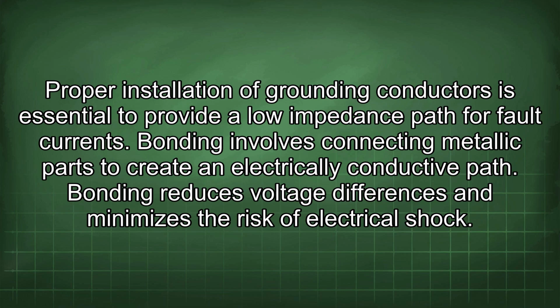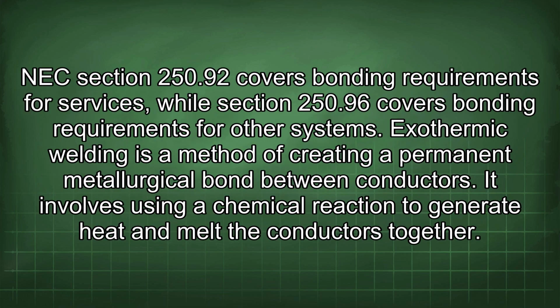Bonding involves connecting metallic parts to create an electrically conductive path. Bonding reduces voltage differences and minimizes the risk of electrical shock. NEC Section 250.92 covers bonding requirements for services, while Section 250.96 covers bonding requirements for other systems.